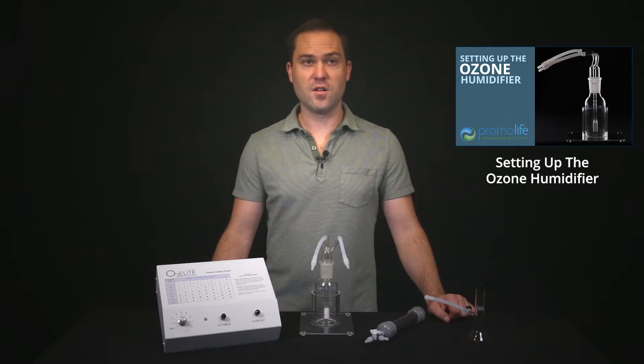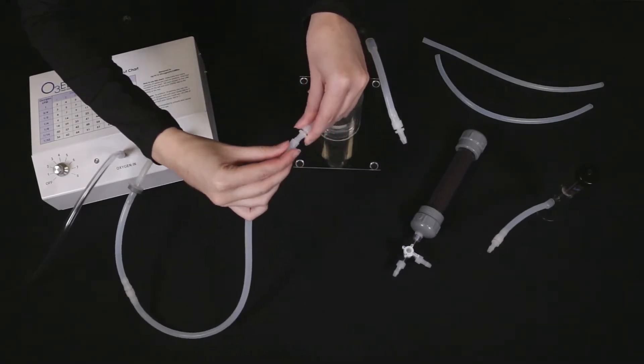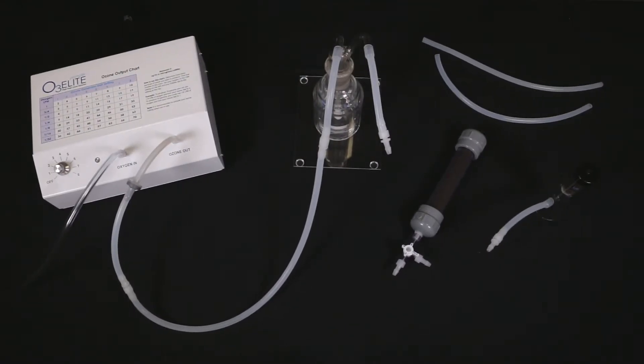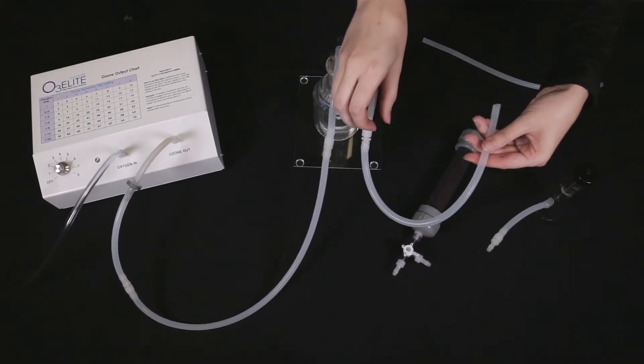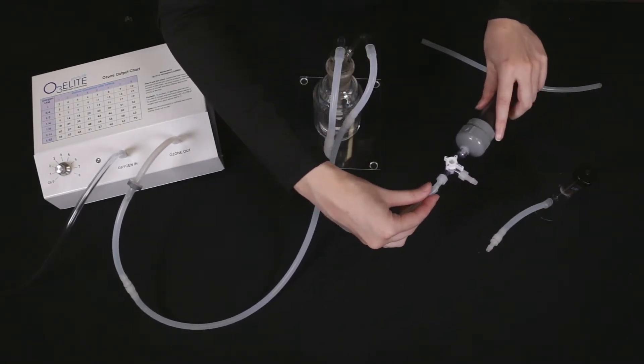For instructions on our 500ml humidifier, please view our video on setting up the ozone humidifier. Back to the 200ml humidifier: connect the other end of the 5 feet of silicone tubing to the glass straw that goes all the way into the humidifier — we also call this the ozone in-straw. To connect the destruct, take one of the 3-foot sections of silicone tubing and connect one end to the other straw of the humidifier, the ozone out-straw, and the other end to the destruct.